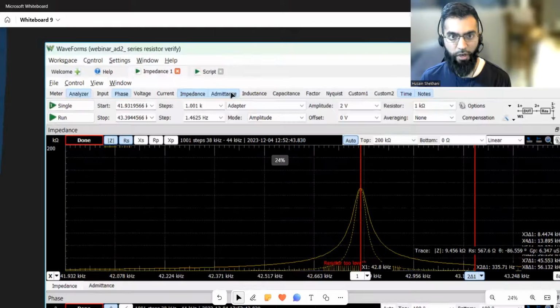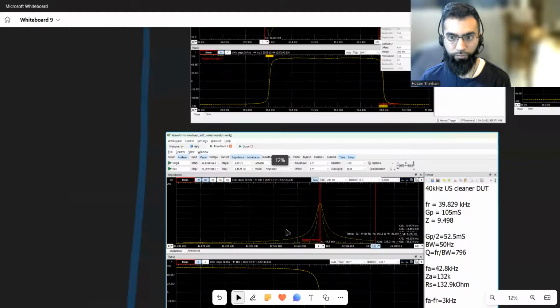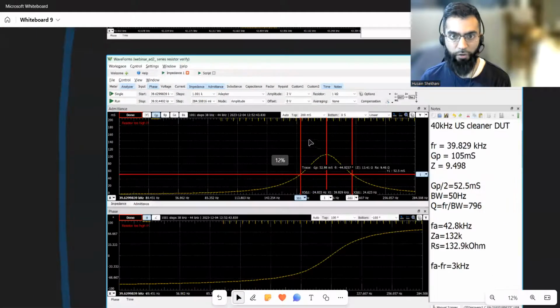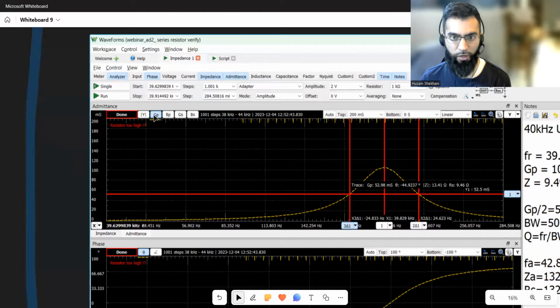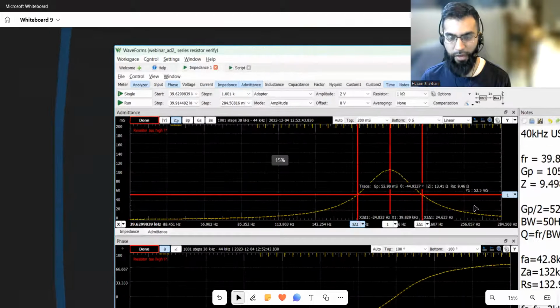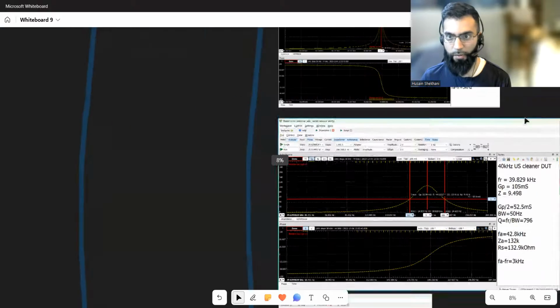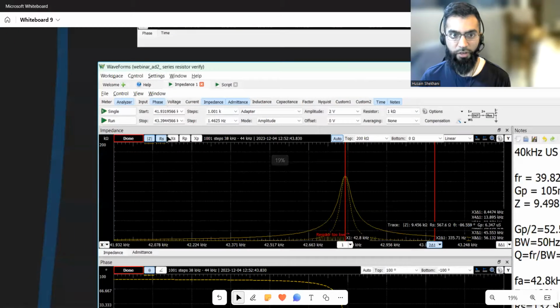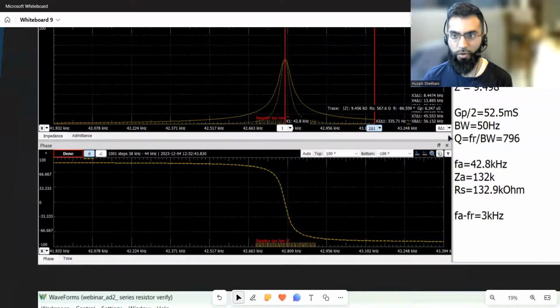parallel conductance, if you click admittance, which I'm showing here, and you click GP, which is parallel conductance, you'll get a peak, which is going to relate to your, as I like to say, real admittance, and that'll give you a peak only related to the LCR circuit. And if you go into the impedance section and click RS, then it'll give you the peak related to the anti-resonance only. And then you look for the bandwidth at half the maximum value in order to calculate the quality factors. And I wrote all those numbers down here, like resonant frequency, parallel conductance, impedance, bandwidth.